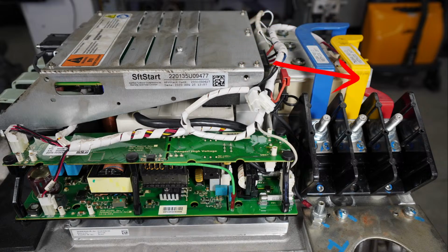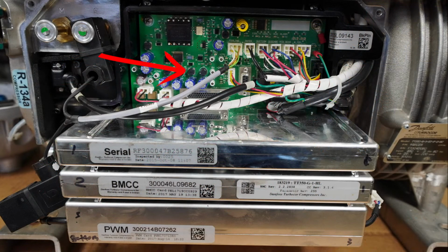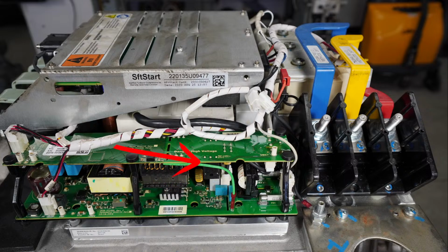bank. So these SCRs are then going to convert that AC power to our DC bus, which is right in here. So this DC bus feeds our capacitor bank on the backside, our inverter here, this is our soft start module on top of the inverter, and then it also feeds our DC to DC converter. What powers our backplane board, so this whole assembly here is our backplane, is the DC to DC converter. So we're taking 600 volts DC off of our DC bus here and feeding into our DC to DC converter.